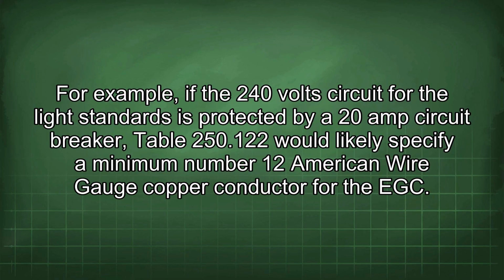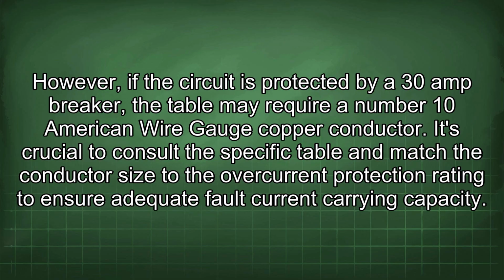For example, if the 240 volt circuit for the light standards is protected by a 20 amp circuit breaker, Table 250.122 would likely specify a minimum number 12 American wire gauge copper conductor for the EGC. However, if the circuit is protected by a 30 amp breaker, the table may require a number 10 American wire gauge copper conductor. It's crucial to consult the specific table and match the conductor size to the overcurrent protection rating to ensure adequate fault current carrying capacity.